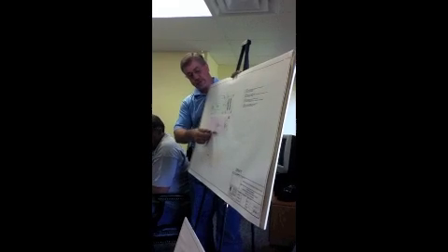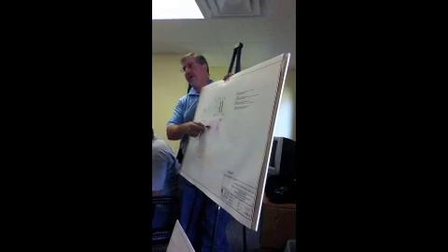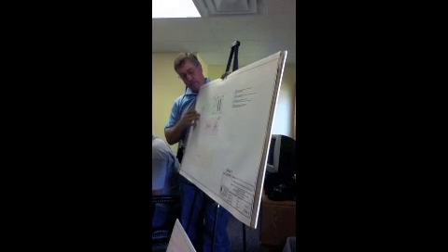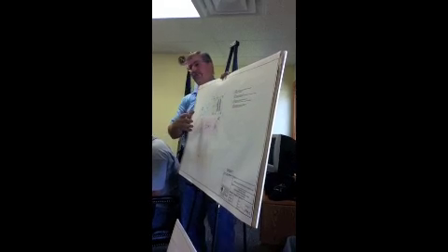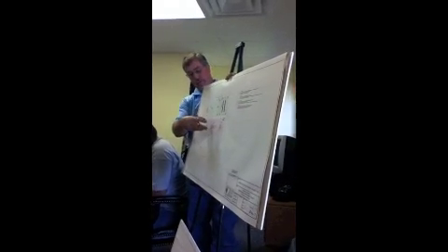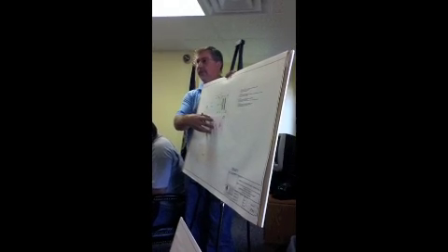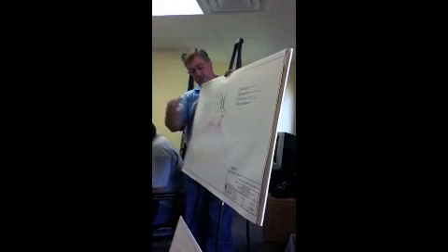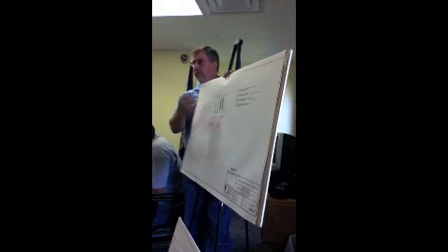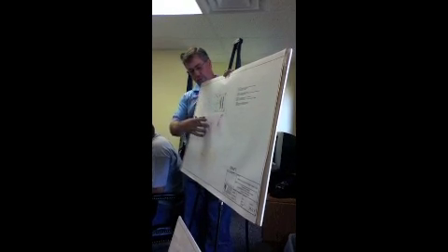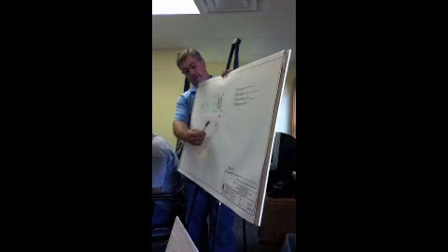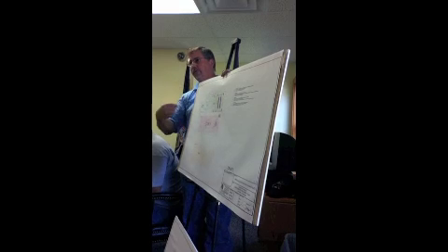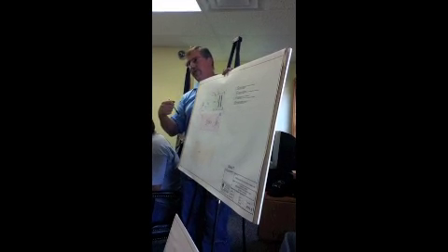What you have now is called an SBR, a sequencing batch reactor. The raw wastewater comes into this plant, and this is everything. It's kind of difficult to put it in layman's terms. But your bacteriological actions take place in here, your biomass is in here. This tank will aerate and mix while your raw sewage is coming in, and then for a period of time it shuts off and settles. The clear water is pumped off the top of this into this tank, which then goes through your sand filtration, microfiltration units.